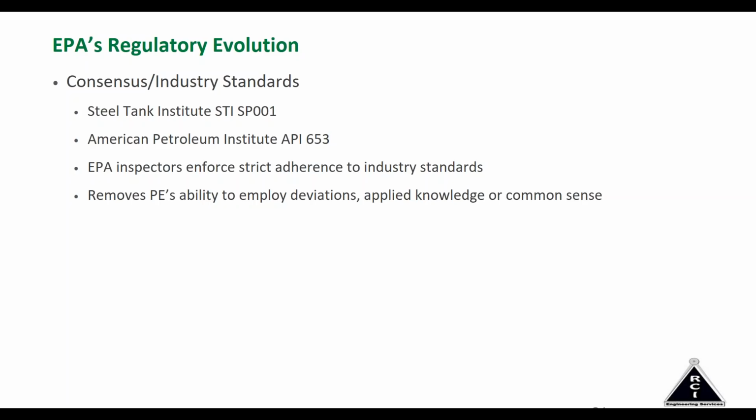But the two that they are citing right now is the Steel Tank Institute's STI SP001 standard, which is primarily a standard for shop fabricated steel tanks used in flammable and combustible material storage. So your fuel tanks. And so any kind of a fuel tank that's a UL fuel tank that's manufactured by a tank manufacturer that's basically designed for fuel storage is going to fall under this Steel Tank Institute standard.